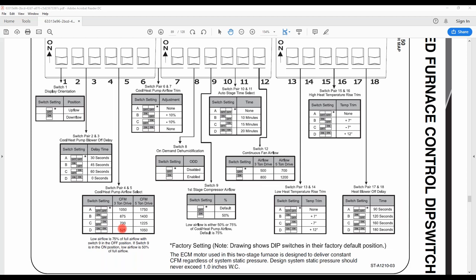So there are options there to get your airflow even lower should you need it, or to better dehumidify using a 2.5-ton unit on a 5-ton drive. So any questions on that at all? That seems to be a little bit of a question sometimes on more application. Some guys do run into that every once in a while. All right, moving to switch number 8. That's on-demand dehumidification. We don't really get into that a lot. Should you have questions on that, just let me know.